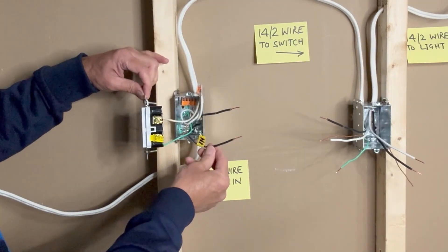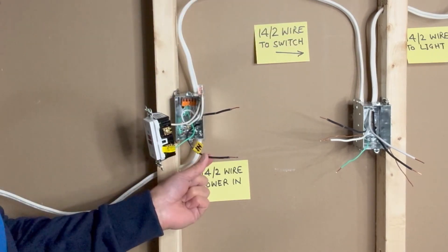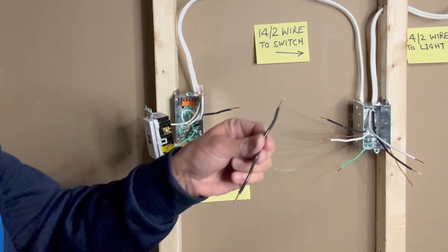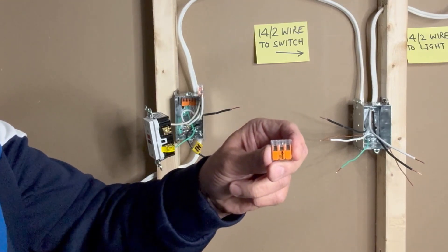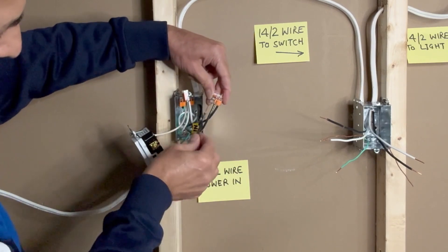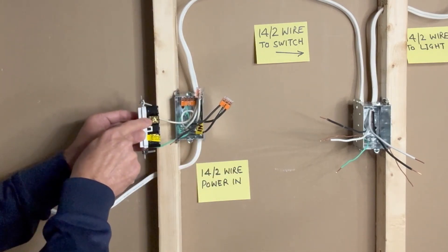Next, I will connect the black hot wires. I have one black hot wire going to the switch box and one black hot wire bringing in power to the outlet box, plus a black pigtail that I will connect to the GFCI outlet. I will use a 3-pin WAGO 221 connector to connect all black wires. This black pigtail will be connected to the top brass (line) terminal of the GFCI outlet.